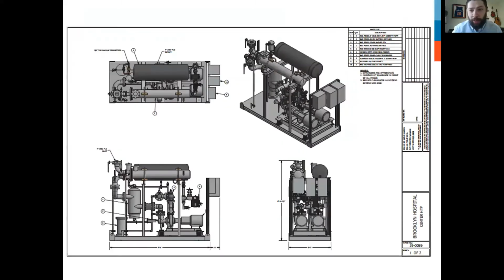And let me show you this layout we did, because I think it's awesome. So if you can see the steam trap basically halfway down there, we've got the pump. We put an angled triple duty valve to keep this thing shorter. All your air separation equipment and your pot feeders all right here. So that's feeding into the water side, and then you've got your hot water out flange facing upward at the top of that thing. Just a beautiful design.